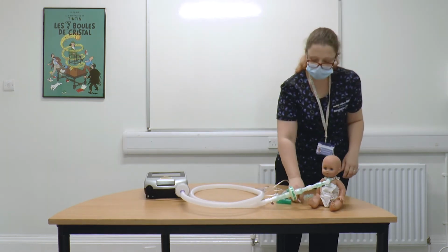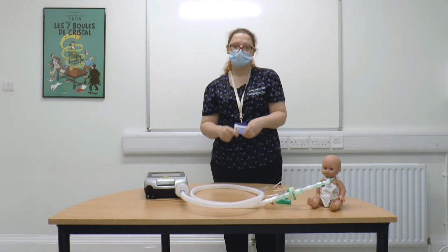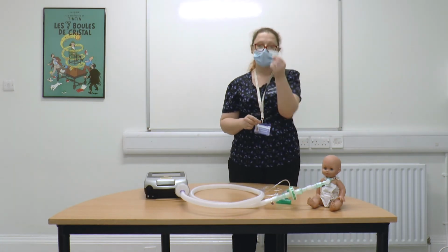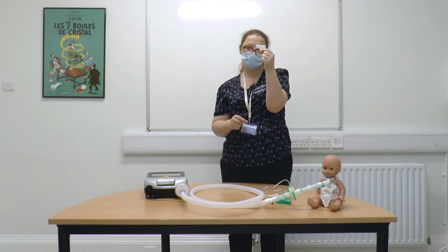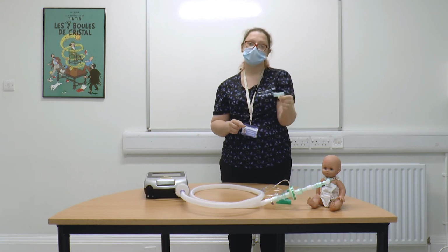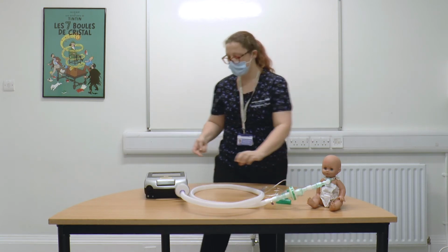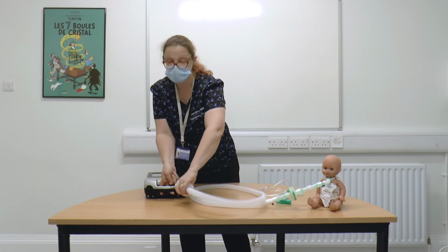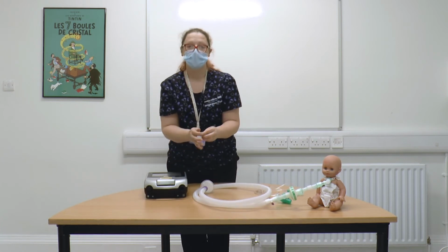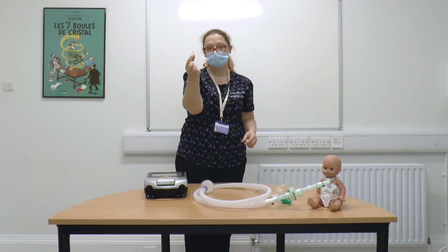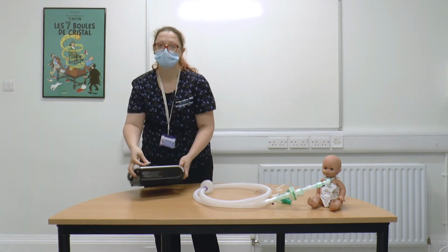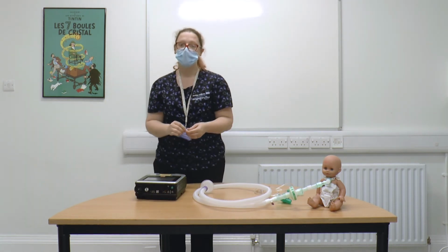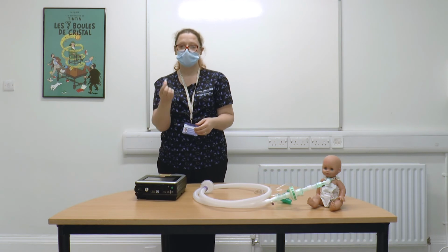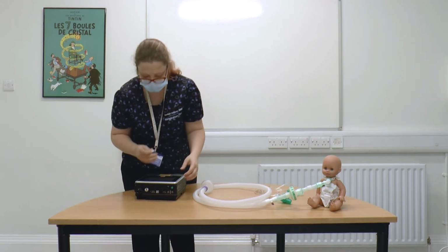If you have a child that has narrower tubing, the 15mm tubing, your oxygen port will be narrower to fit with it. Again, it's front of circuit, so maximum 5 litres. If you have a child that has an Astral or a Trilogy, they will have a white plastic port in their bag, if they're a child that doesn't always have oxygen. If they have always got oxygen, it will already be inserted in the ventilator.